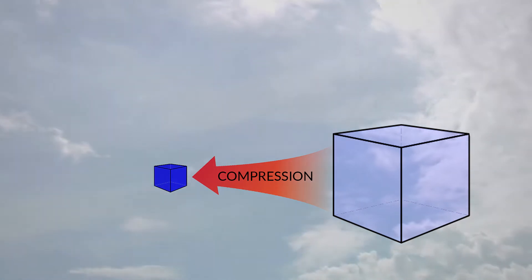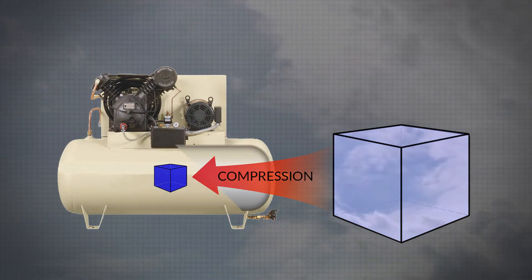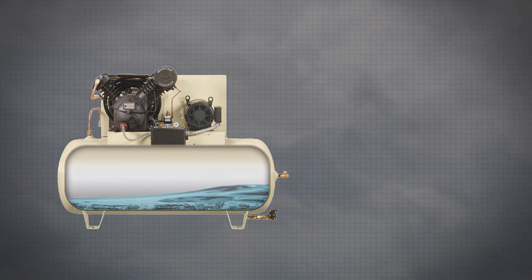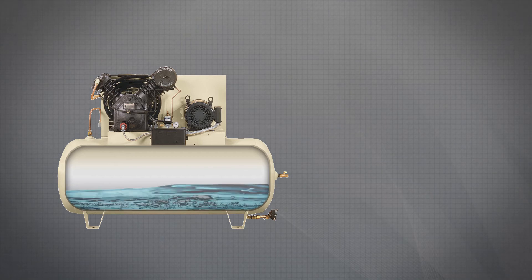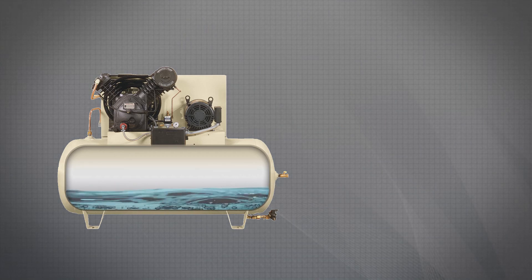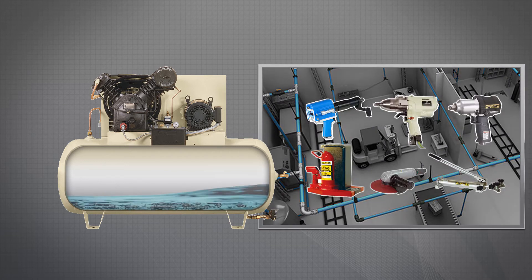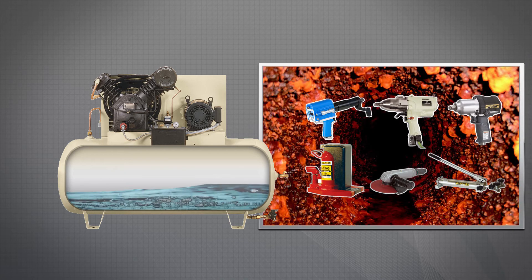Air naturally contains humidity, and when air is compressed, it transfers that moisture into the air tank. As the compressed air is cooled, condensation collects in the bottom of the tank and must be removed. Draining this condensate is a necessity for the compressor to operate effectively, because it prevents moisture from getting into the lines and air tools, and also prevents the development of corrosion, which increases the safety of operation.